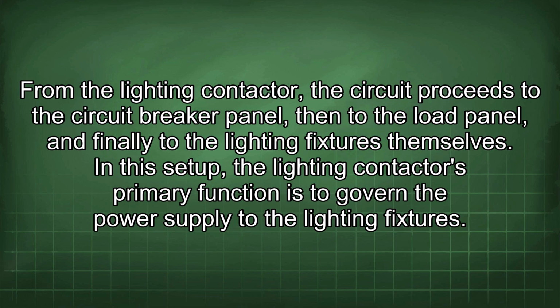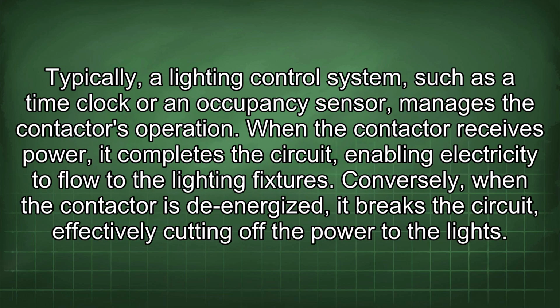From the lighting contactor, the circuit proceeds to the circuit breaker panel, then to the load panel, and finally to the lighting fixtures themselves. In this setup, the lighting contactor's primary function is to govern the power supply to the lighting fixtures. Typically, a lighting control system, such as a time clock or an occupancy sensor, manages the contactor's operation.